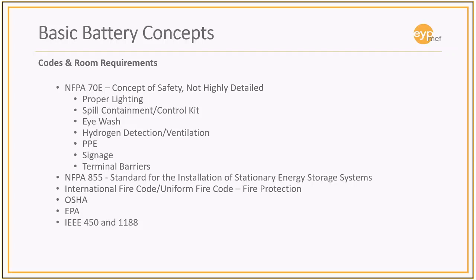When you look at lithium-ion batteries, part of their total cost of ownership is that they have a very small footprint. But some of the requirements around the new codes are that you separate these battery configurations in certain quantities. I believe it's 250 kWh size increments of batteries are separated by 3 feet from each other and 3 feet from a wall. So the size of the battery room tends to get larger and larger.